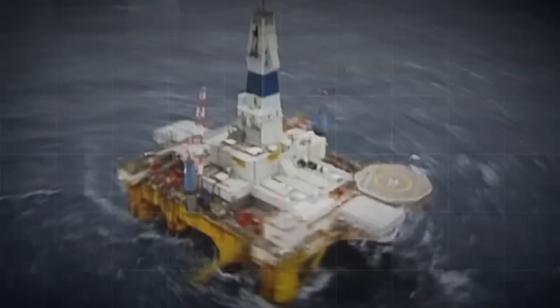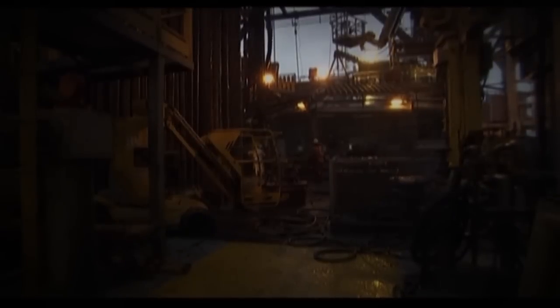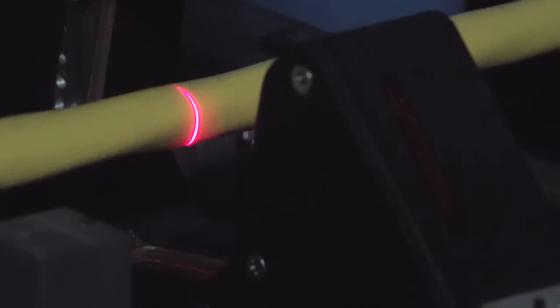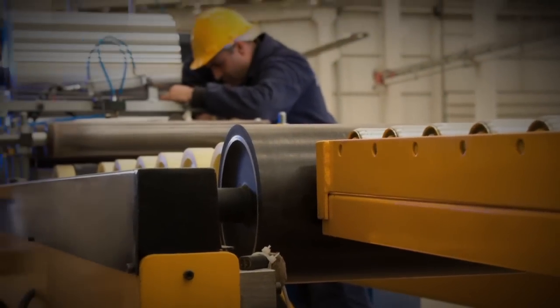But fiber optic cabling in industrial environments differs in significant ways from that of traditional enterprise networks. Temperature and humidity may fluctuate, vibration may be a factor, and motor noise can interfere with data transmission, while chemical and oil exposure often threatens long-term reliability of cabling. Cable materials used in traditional fiber optic data networks may be unsuitable for the harsh conditions found in manufacturing environments.